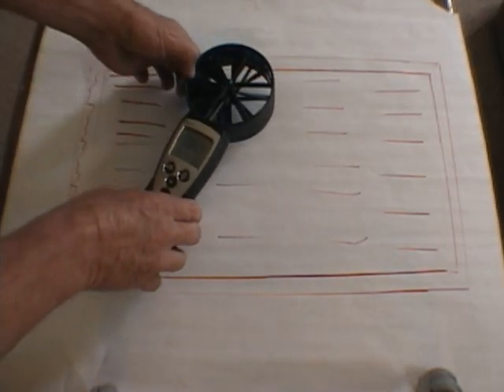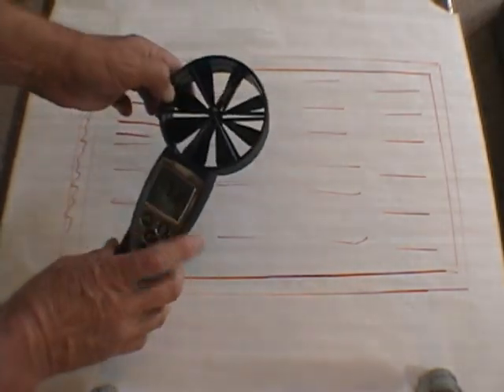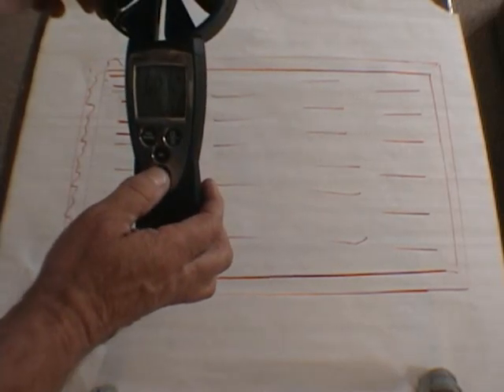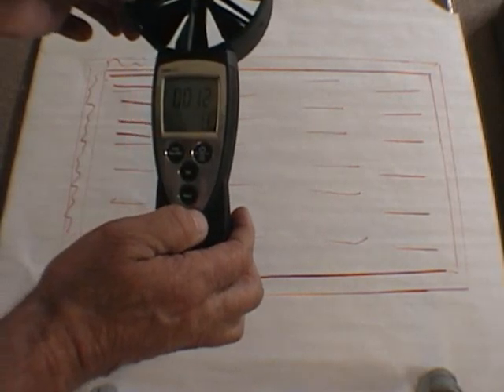The timer will start timing, and as we traverse it's going to time our traverse. As soon as we get finished traversing, we hit the timer again, the timer stops, we can push this mean button one more time, and it's going to give us our average feet per minute for that traverse.